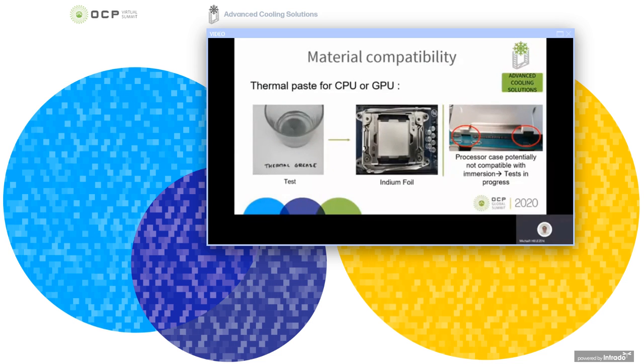Most processors are sealed and do not present any problem while immersing into a dielectric liquid. However, some processors have slots which invite liquid to enter, driving CPU malfunction. The appearance of the problems can vary over time depending on the liquid composition. On the right picture, you have an example of slots issue on a CPU. You must check that the selected processor will match accordingly.